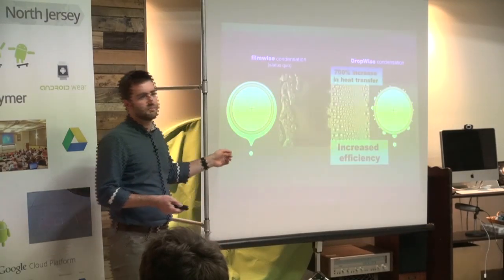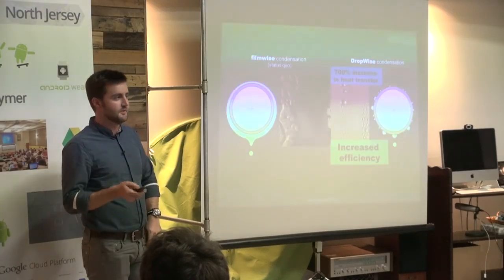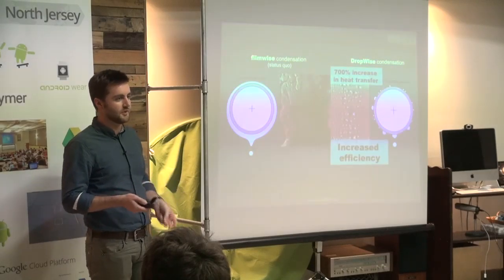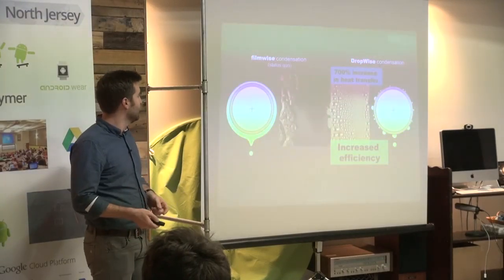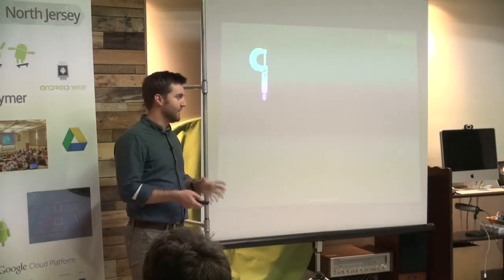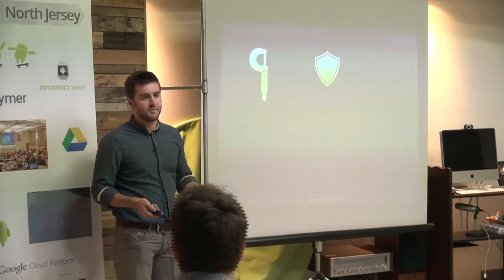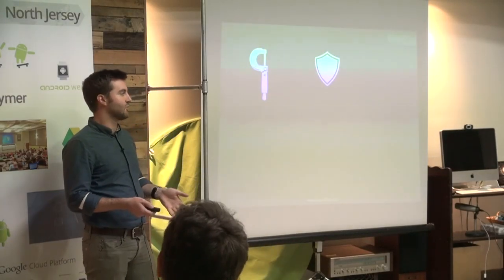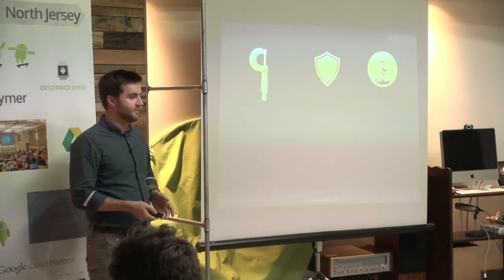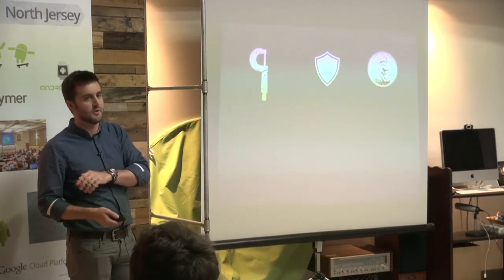This is old news — people have tried to make coatings like this happen for almost a century now, but nothing has worked because nothing has been able to solve the three fundamental challenges. First, the coating has got to be really thin — even a micron is too thick. Second, it's got to be very durable, because steam is an incredibly aggressive environment and degrades most coatings within minutes. And last, it's got to be really cheap, because the plant wants to make back the expense of applying the coating very fast.